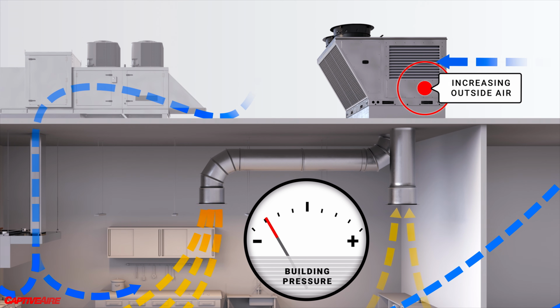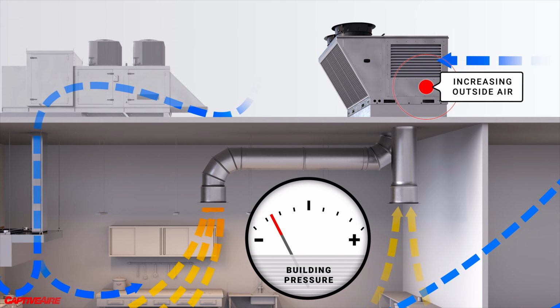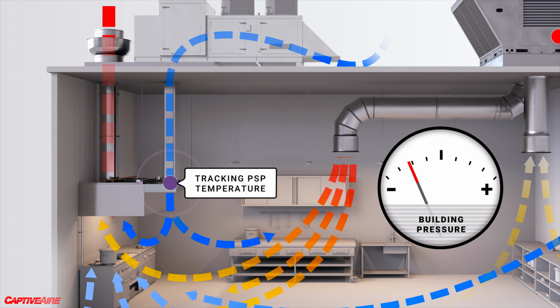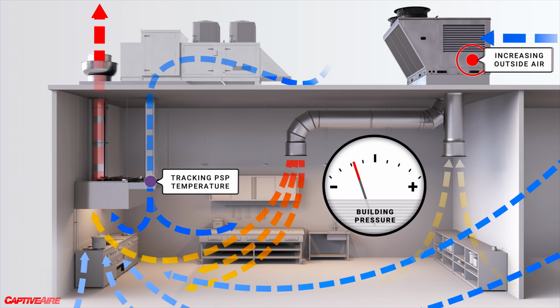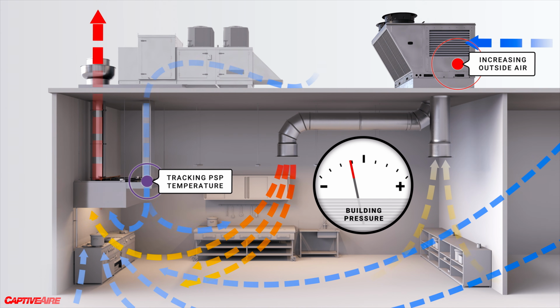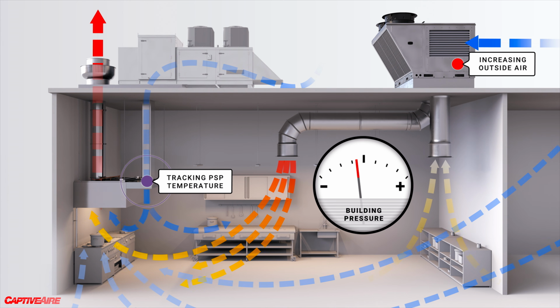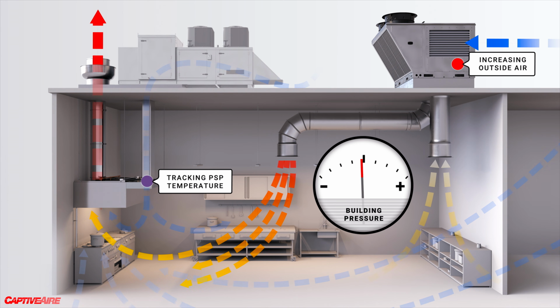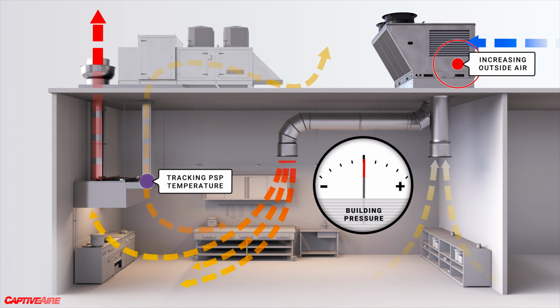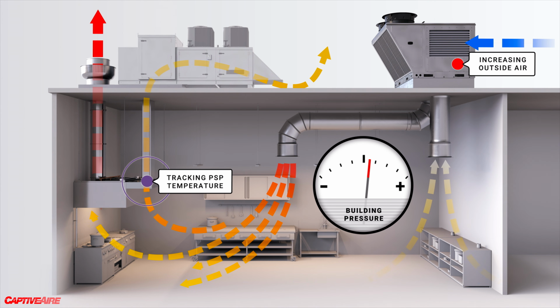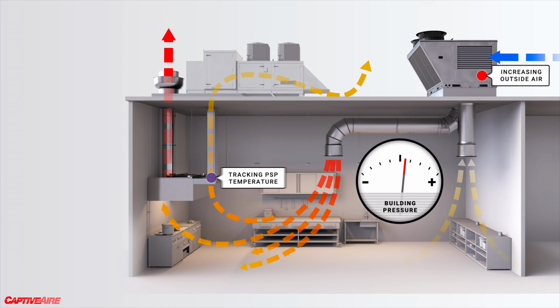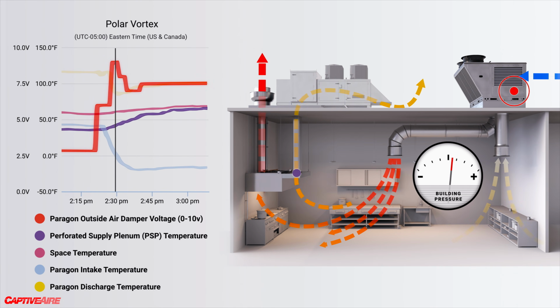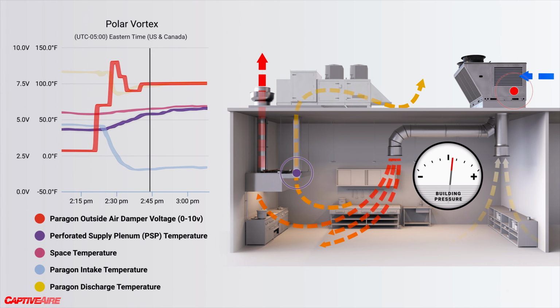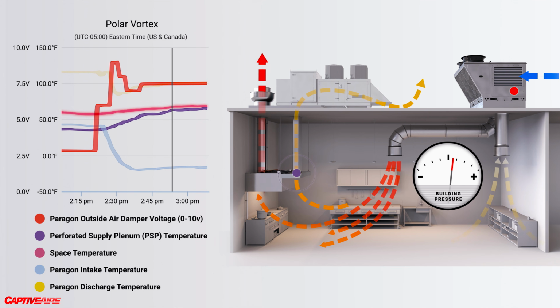So what I did to track this is I slowly started increasing that outside air damper by about a half volt to a volt in 2-minute increments, and then tracking what the PSP temperature sensor in that hood was now reading. Because keep in mind, if the building is negatively pressurized, air is going to be coming in, so that PSP reading is going to be very cold. Now, if we get to a point where we're actually getting slightly positively pressurized, now air from the space should be going up through that PSP, so our temperature should be reading closer to what that space temperature is. So I kept tracking that up until we got to a point where that outside air damper was reading a PSP temperature that looked like the space temperatures. And at that point I said, all right, we are now space neutral.